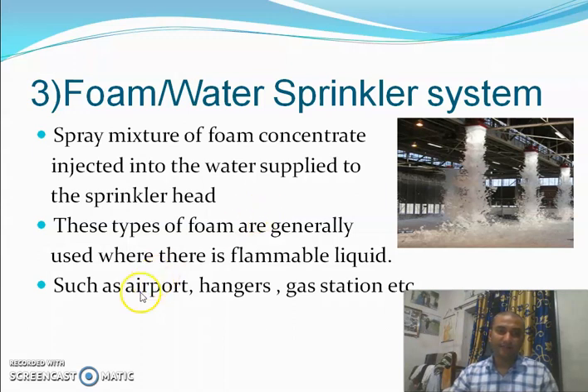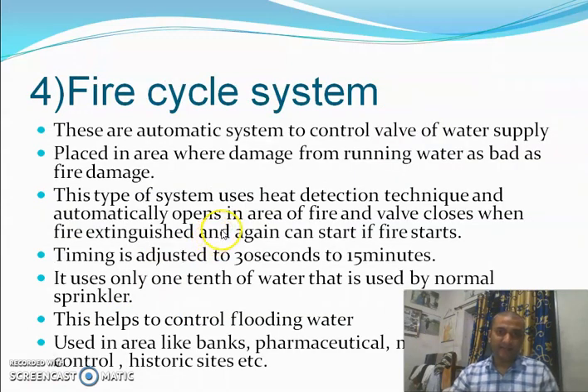Now moving towards the next topic, the fire cycle system. This is an automatic system to control the valve of the water supply. It is placed in areas where damage from running water is as bad as the fire damage. This system uses heat detection techniques and automatically opens in the area of fire, and the valve closes when the fire is extinguished, and can start again if the fire restarts. The timing is adjusted from 30 seconds to 15 minutes. This uses only 1/10 of the water used by a normal sprinkler, so we can say that fire control is also good and the use of water is reduced.